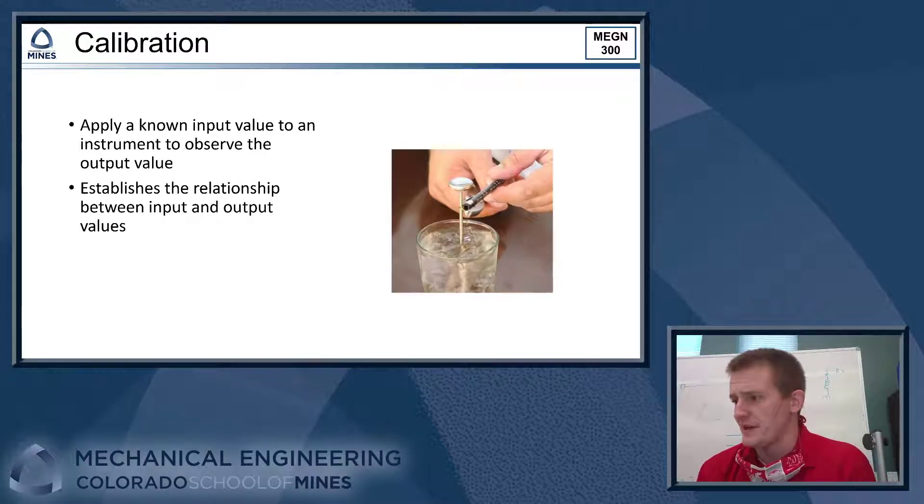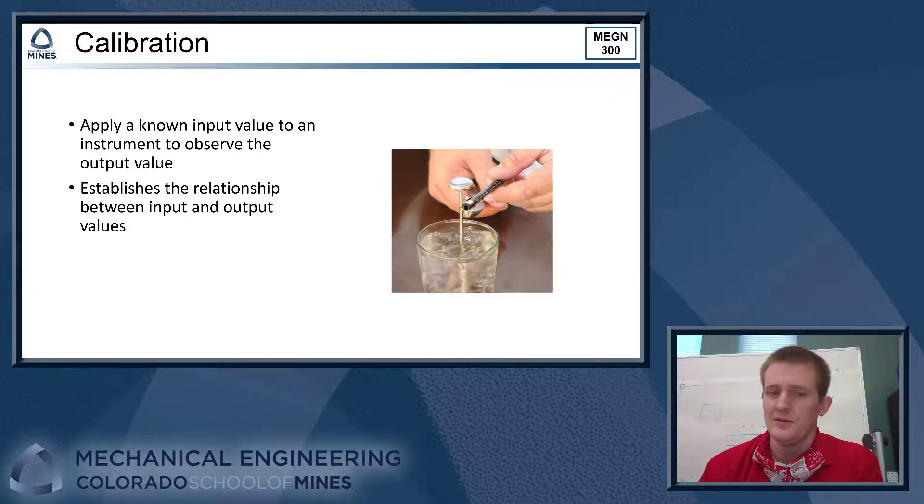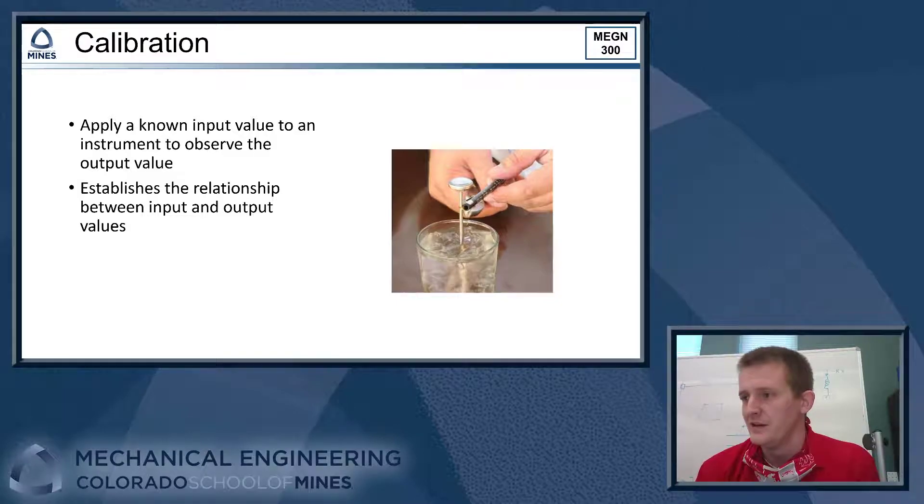All right, so first of all, let's talk about what calibration is generally. Calibration is the process of applying a known input value to an instrument to observe the output value. We want to establish a relationship between input and output values for an instrument so we can correct for any bias errors. So here we've got a picture. We've got a thermometer going into a glass of ice water. Melting ice will be zero degrees Celsius. We have a known temperature that we can apply to this thermometer to see if its output reading is correct and adjust it if necessary.